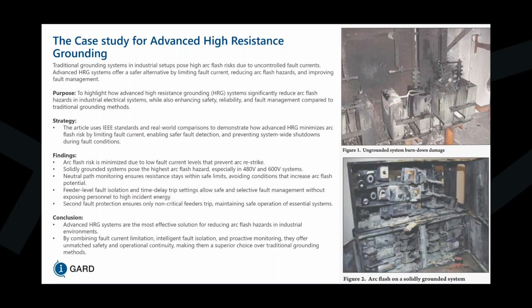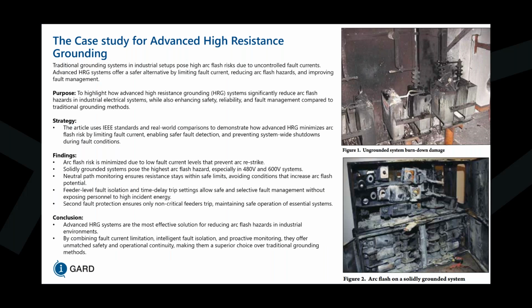Now, here's the case study for advanced high resistance grounding. Traditional grounding systems in industrial setups pose high arc flash risk due to uncontrolled fault currents, particularly for solidly grounded systems. And for ungrounded systems, it's possible that there could be 2 faults in the system at the same time, since it's very difficult to locate faults in an ungrounded system.